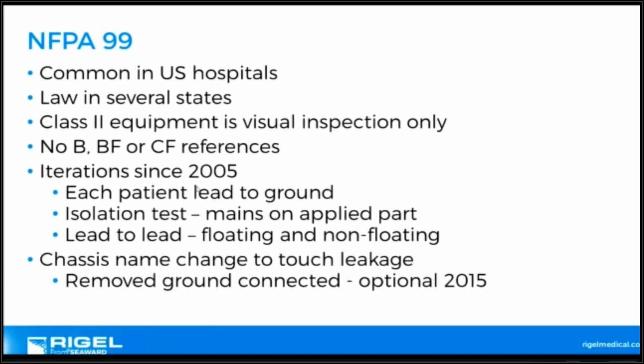So, you have the Joint Commission, and then you've got various agencies and regulatory authorities giving you guidance on how you should do testing. Well, the NFPA 99 has been kind of watered down over the years. So you used to do patient lead to ground, which is pretty much your patient leakage, your mains and applied part, and your patient lead testing. And between leads, you don't do that anymore. All of these tests have been taken out.